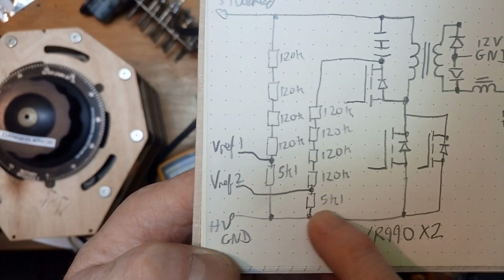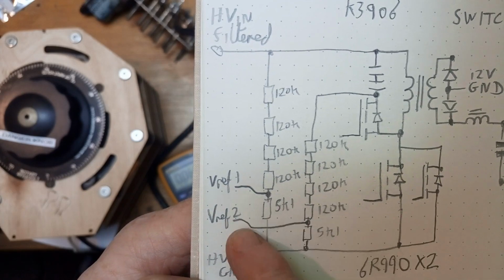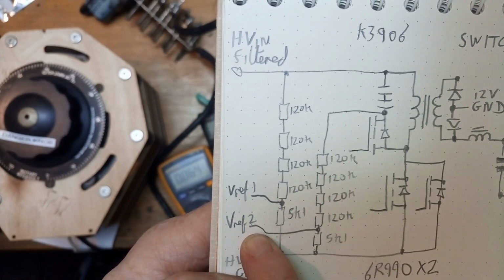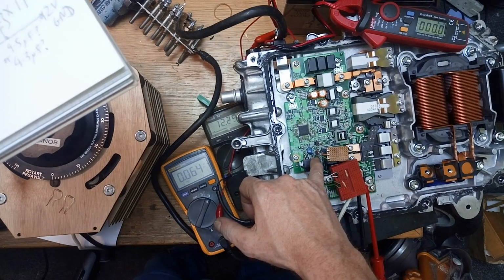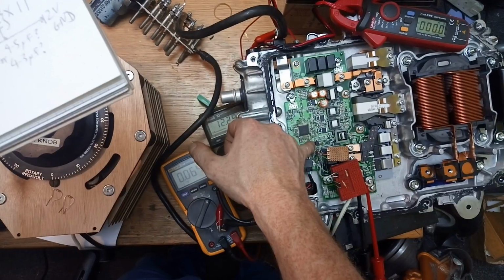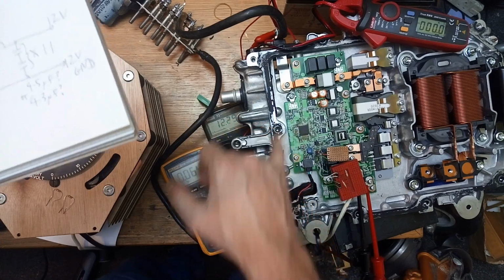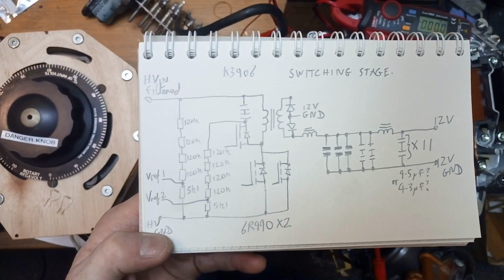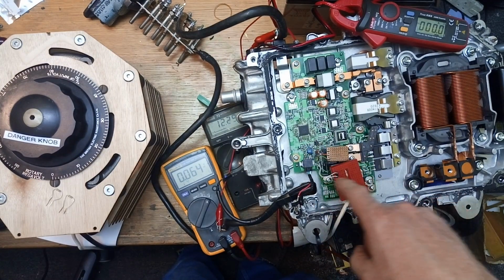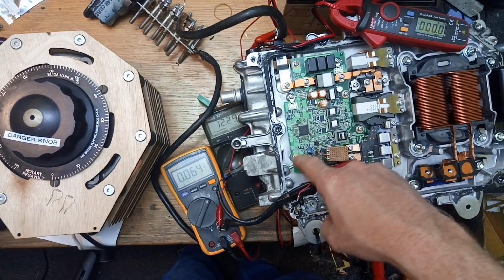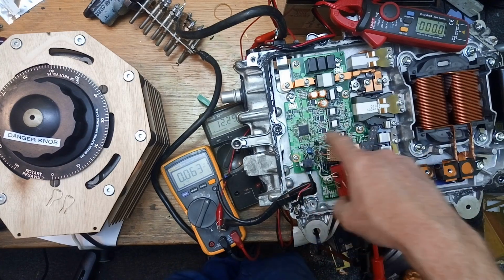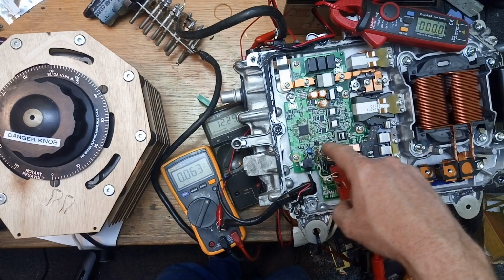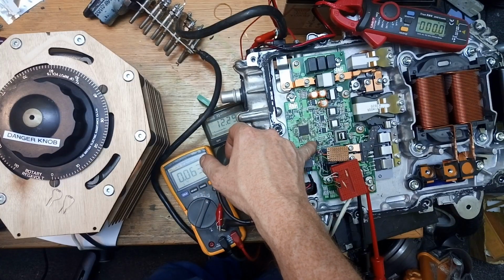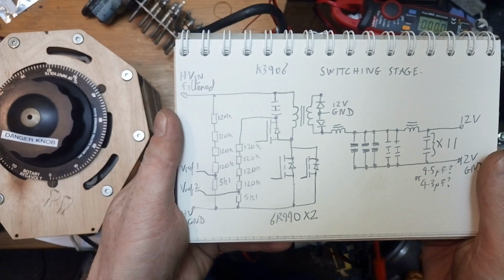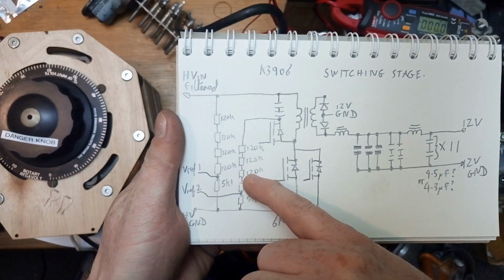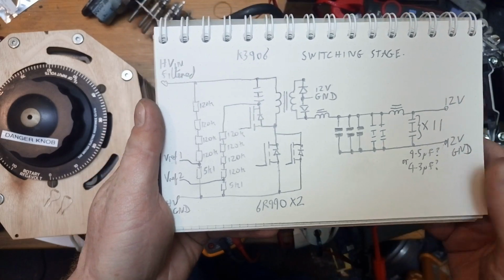So these 2 voltage dividers, which I've labelled Vref1 and Vref2, go through what looks like a couple of op amps in this area, and then through an optical isolator to the main controller. Because when you hold this board up to the light you can see a physical light band around the isolation gap between the high voltage and low voltage, you can see that is the only link between high voltage and low voltage. So it left me wondering if this really was the threshold detection for shutting the DC to DC converter down.